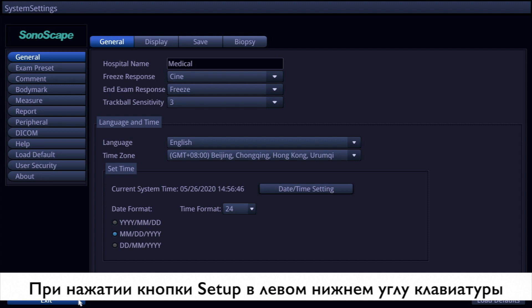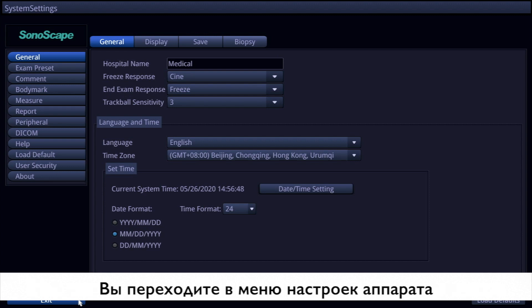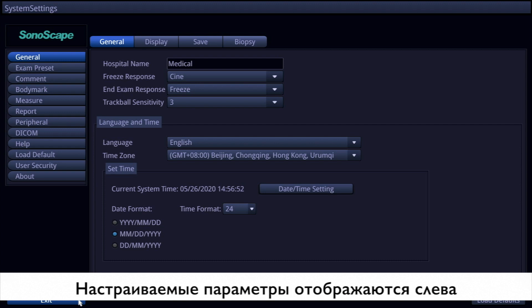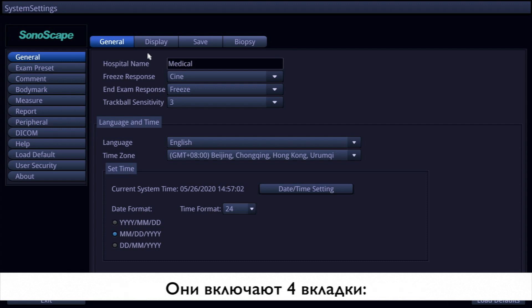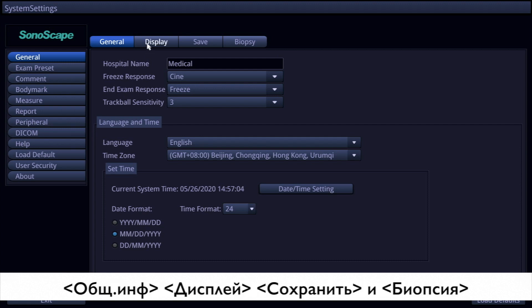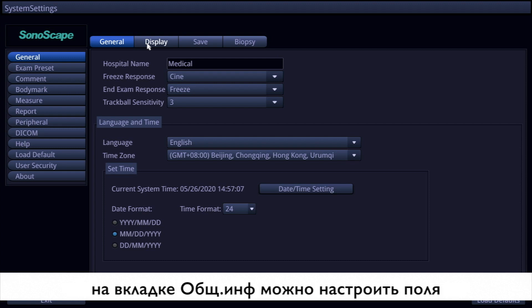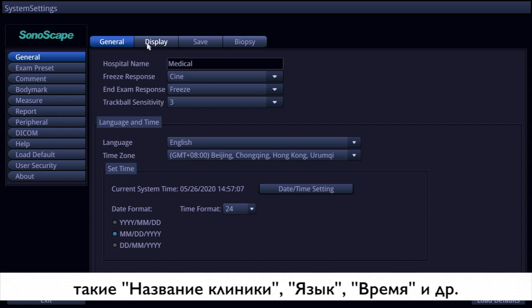By pressing the setup button in the lower left corner of the keyboard, you will go into the setting interface. There are different buttons on the left side of the interface showing how many items you can set up. First, it's about the general settings — there are four pages including general, display, save, and biopsy. On the general page, it covers hospital name, language, time, etc.